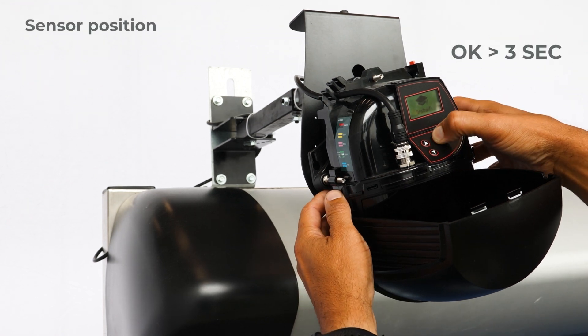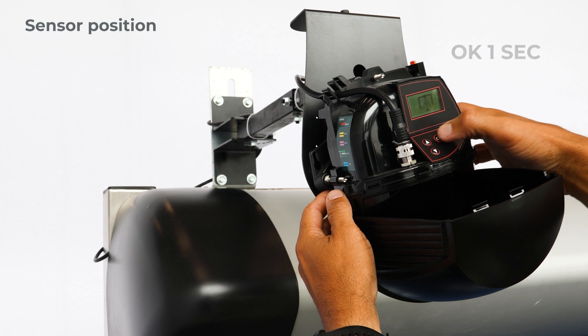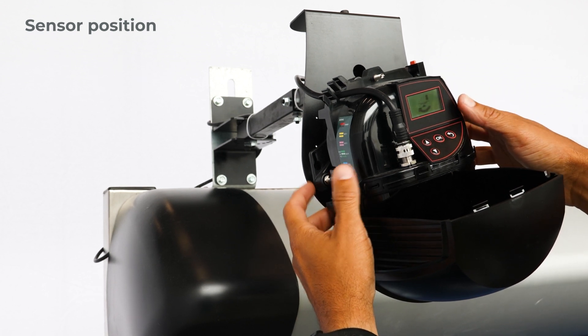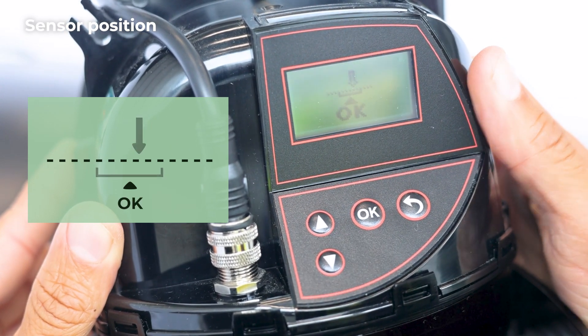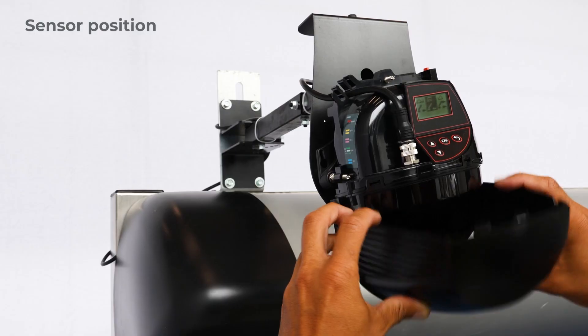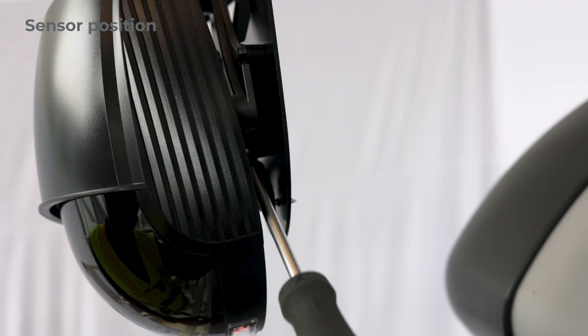Push the OK button below the LCD screen for more than 3 seconds to enter the center tool. Push once more to start. Adjust the lateral position of the sensor until the arrow is positioned in the bracket and push OK. Press OK to confirm. Close the sensor and lock its position.